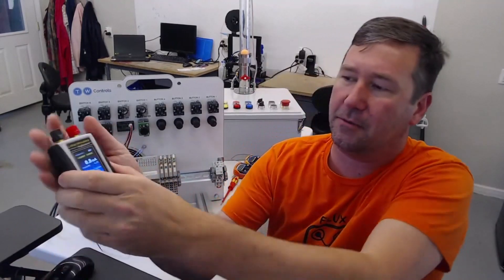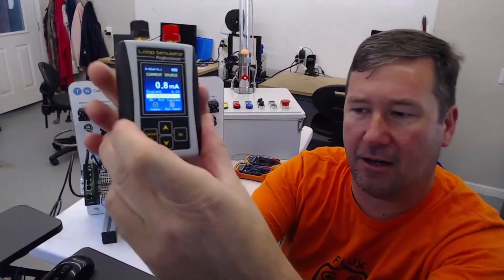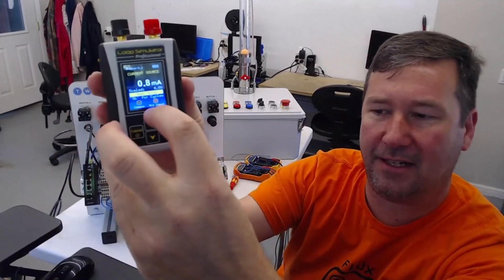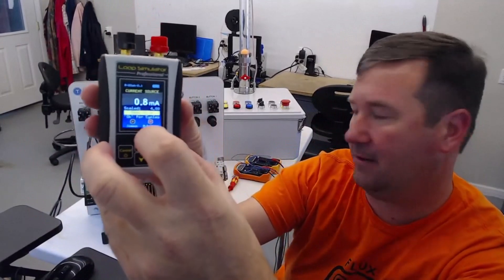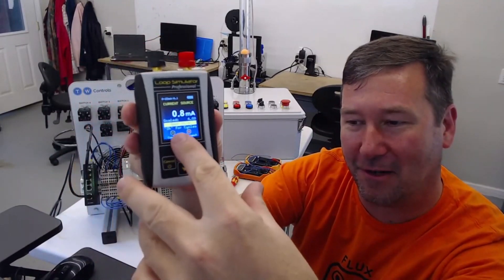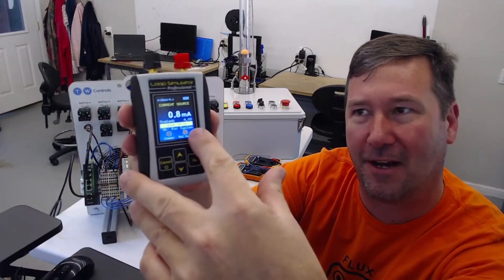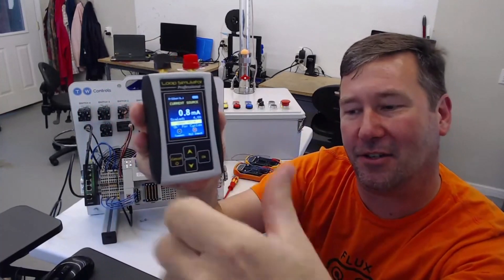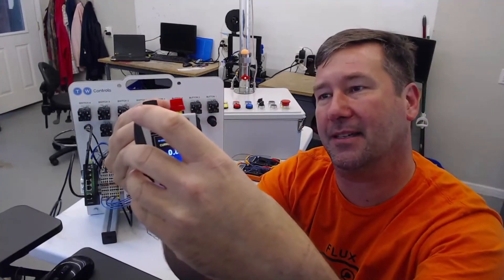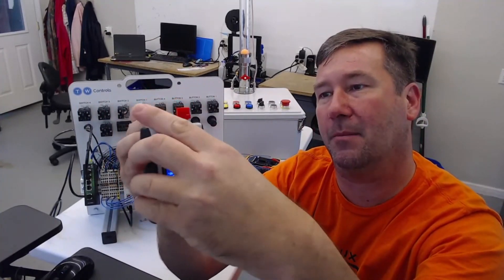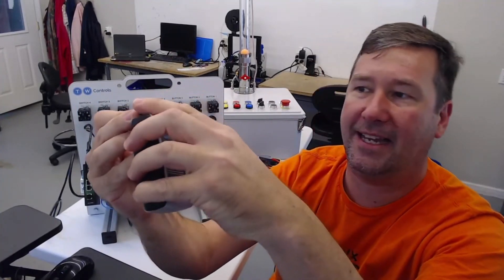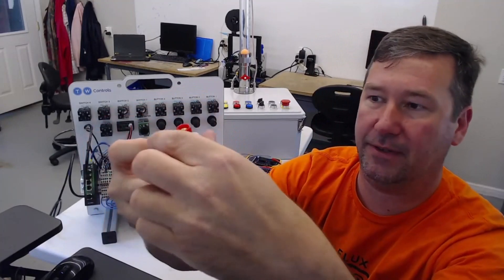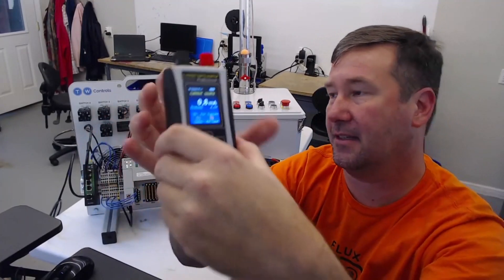One of the neat features of the loop simulator, and the reason I knew something was wrong, was with this off you see this open wire banner. I apologize, my wires are short and my camera is in the wrong position. It says open wire right here, and that told me something was wrong with my analog circuit. That's one of the best features about this. If I hook the wire back up, or in that case I just had it hooked to the wrong style of input, then it's going to show something here.